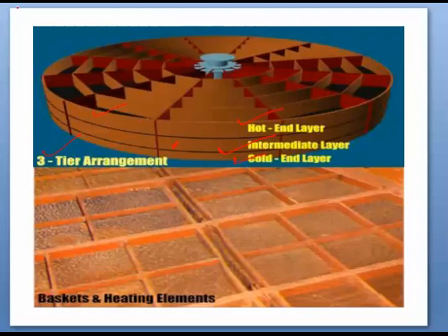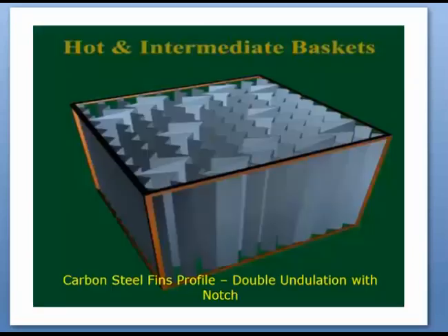And as we discussed earlier, all these segments are filled with heating elements, and they are like this. These are the in-between heating elements which are filled here. In these sectors, the segments are filled with elements which absorb the heat of the flue gas in the first rotation, and when they come across the cold fluid, they release their heat.